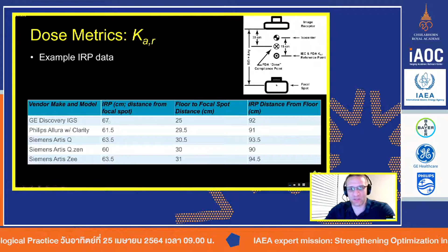And so here I just simply listed a few: GE, Philips, a couple Siemens units. These are systems that have interventional reference points that range from 67 centimeters from the focal spot all the way down to about 60 centimeters from the focal spot. So there is a difference. You can't assume it's all the same. It's always different for every machine. Well, vendor, I should say.